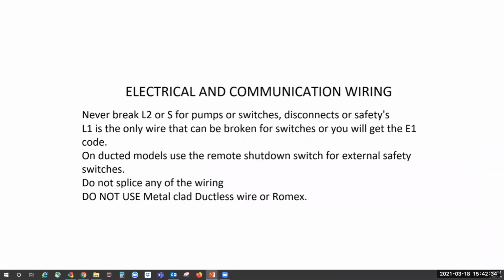A common communication error: you never splice or break the S wire or the L2. If you have to break the wires for a condensate pump or something, you need to break L1. You can't use butt connectors or anything like this. Just no splices whatsoever. Now, sometimes a local code might require a switch, and we'll go over a little bit more of that later.